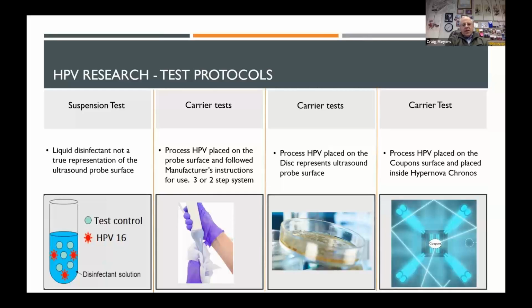Another way that's commonly used is to take the coupon or the disc that's made out of the same material as the probe, as the ultrasound probe. We dry the virus on that. We soak that spot with disinfectant for a certain contact time, and then we stop the disinfectant, we clean up the virus, and we test for residual infectivity.